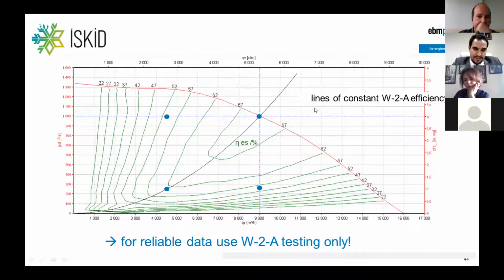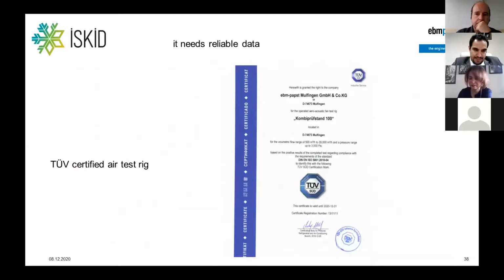So the most efficient and most accurate way is to do some testing. W-2-A stands for wire-to-air efficiency. So as shown before, for a certain duty point, the input power is tested, and with this data, you can be sure to be on the safe side when dimensioning or selecting the fan. It needs reliable data. So for that, it also needs the right test rig. It could be TÜV, it could be AMCA, it could be Eurovent, it doesn't matter, because all these documentation and certification are based on the same physics. In most cases, it's the ISO 5801. Even the AMCA is based on the ISO 5801.